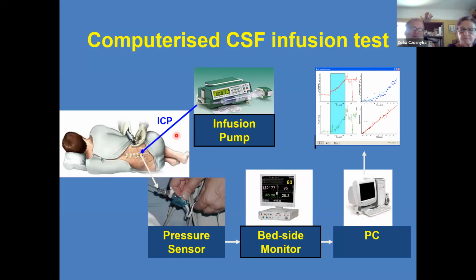And through three-way stopcock, we can deliver fluid with constant rate using infusion pump and also measure pressure with external transducer. Signal from transducer, this is electrical signal, is going to bedside monitor and further through the digital link to computer running software ICM Plus used for analysis of intracranial pressure. I will show this part of the slide in magnification a little bit later, as it's a little bit important. So at the beginning, we measure baseline pressure, and then when we start infusion, we observe increasing intracranial pressure and saturation at certain point.